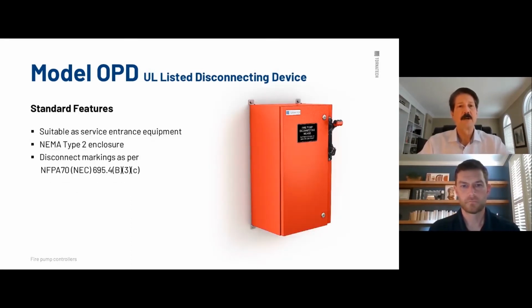Standard features. Obviously, it's SUSE rated, service suitable for service equipment itself, service entrance equipment. So this is going to go off the secondary, the pole, the pad mount, or the volt transformer direct from the utility, and it's going to go in between the source of the utility power and the incoming power of the fire pump controller itself. And it can be done on the normal side and the emergency genset side too. So this is key. You must have service entrance rating.